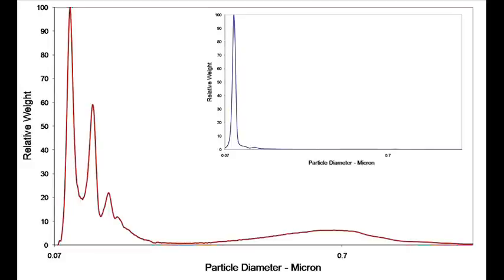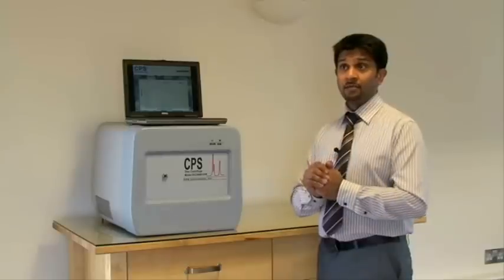We can actually show all of that with the CPS instrument, and as we purify the adenovirus sample, we can remove these agglomerates and show the clean, pure peak. Most techniques, you will actually struggle with the resolution and will be unable to see these agglomerates and aggregates in the sample.